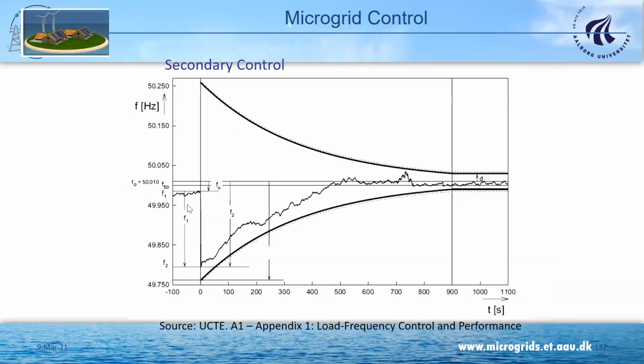This is just one example about the frequency secondary control in the north of Europe. You can see that here we were inside these limits, around 50 millihertz plus or minus, which is still okay. But when we go beyond these limits, we need to restore the frequency within a certain speed—in that case 900 seconds, because it's a large power system. If we're inside this range, we don't need to do anything, so this is kind of a dead band.